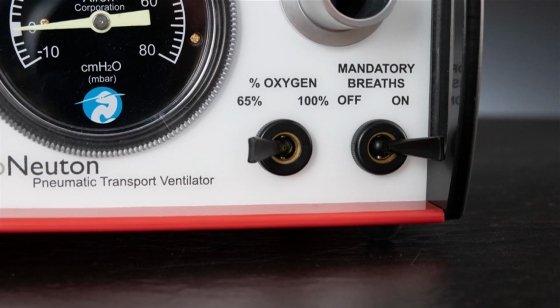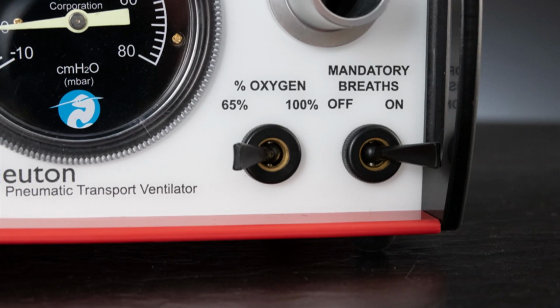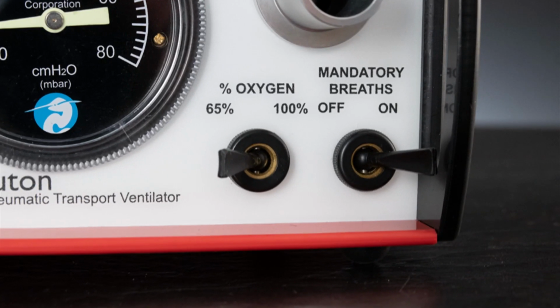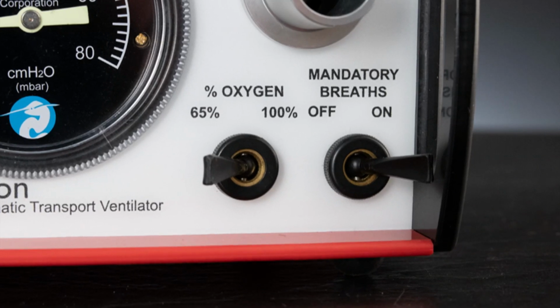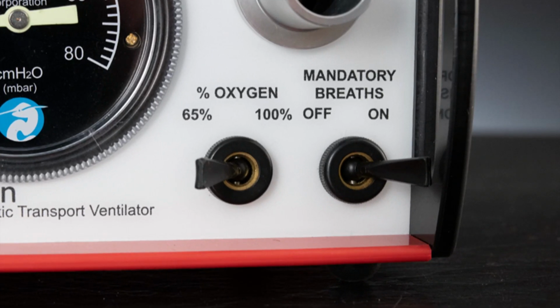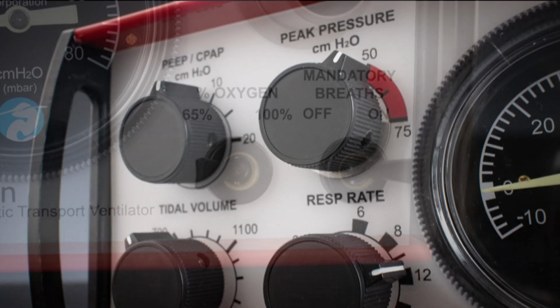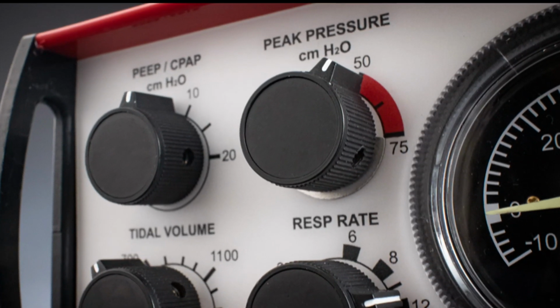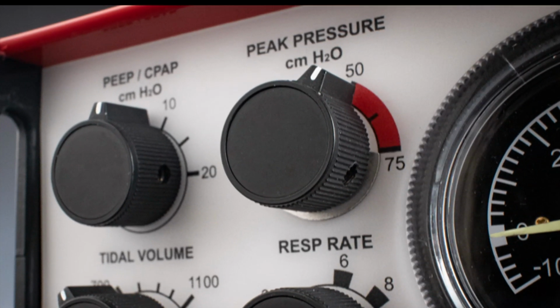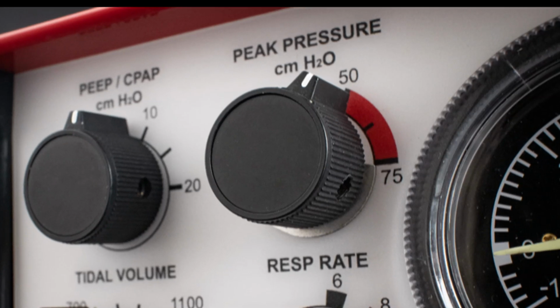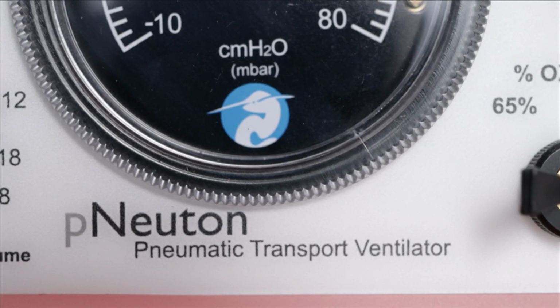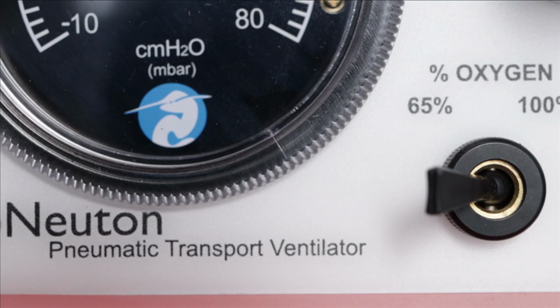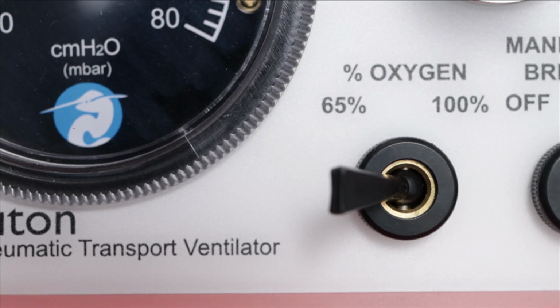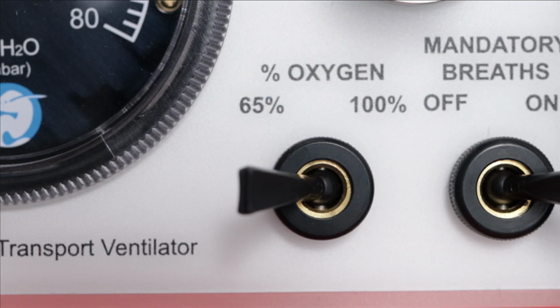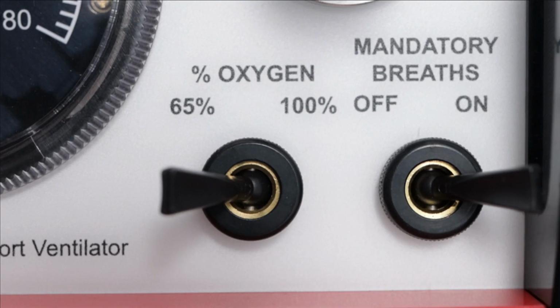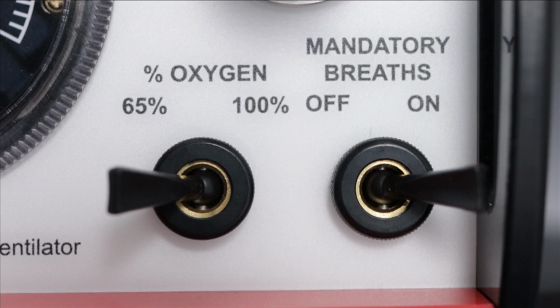When set for 65%, an internal high-flow Venturi system entrains ambient air on the back panel to decrease the FiO2 while maintaining the correct tidal volume. The high-flow Venturi provides stable performance up to the maximum operating pressure, 75 centimeters of water, of the ventilator. With the two oxygen levels, you conserve oxygen with the 65% oxygen setting and can average 45-minute CPAP runtime on a D cylinder.